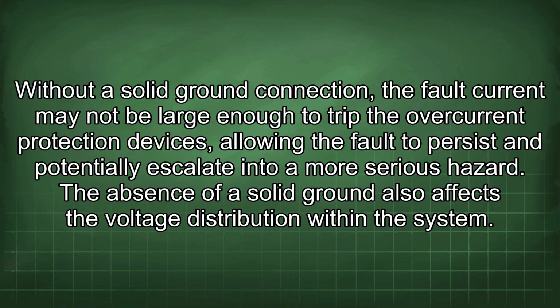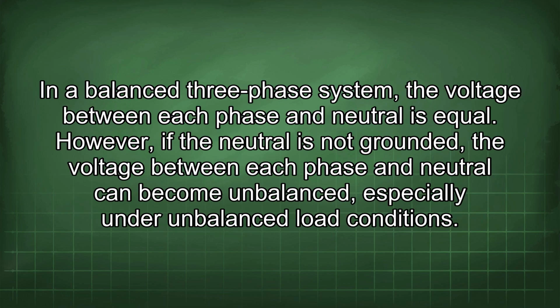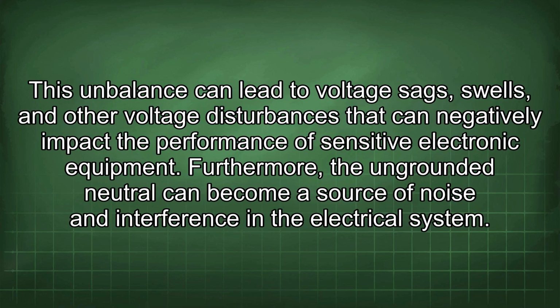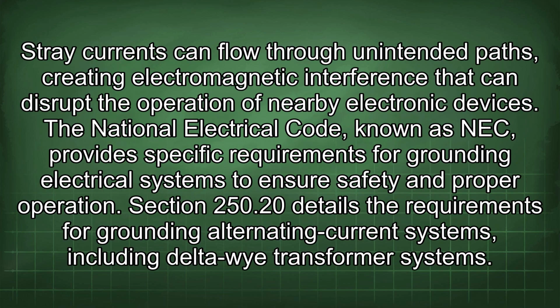The absence of a solid ground also affects the voltage distribution within the system. In a balanced three-phase system, the voltage between each phase and neutral is equal. However, if the neutral is not grounded, the voltage between each phase and neutral can become unbalanced, especially under unbalanced load conditions. This imbalance can lead to voltage sags, swells, and other voltage disturbances that can negatively impact the performance of sensitive electronic equipment. Furthermore, the ungrounded neutral can become a source of noise and interference in the electrical system. Stray currents can flow through unintended paths, creating electromagnetic interference that can disrupt the operation of nearby electronic devices.